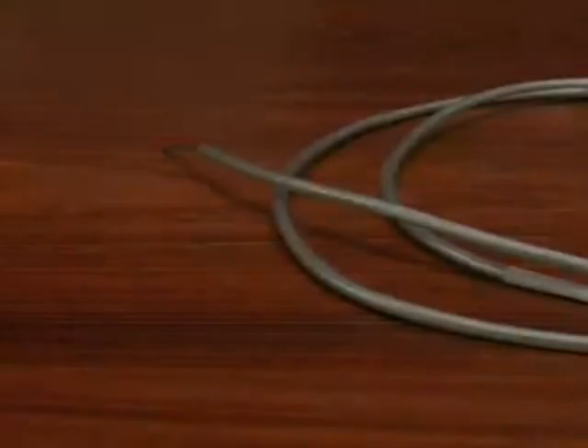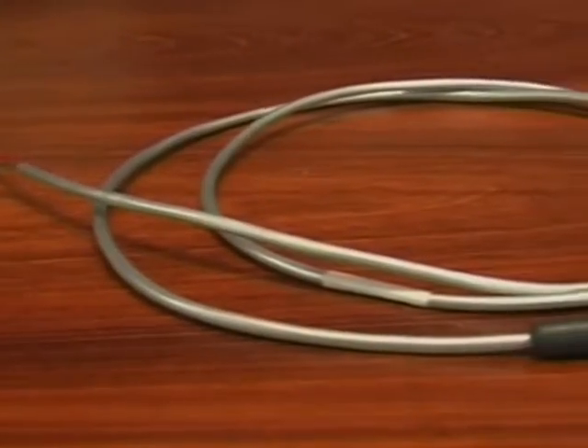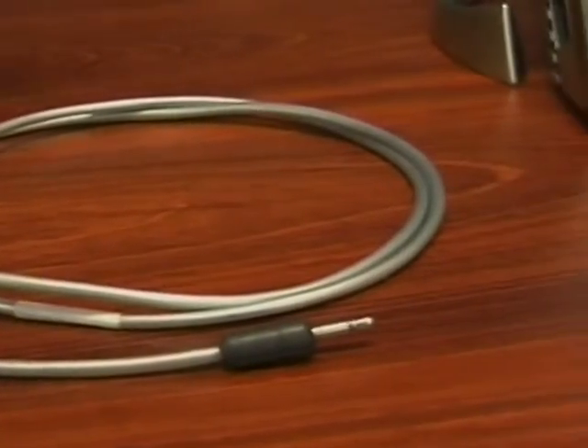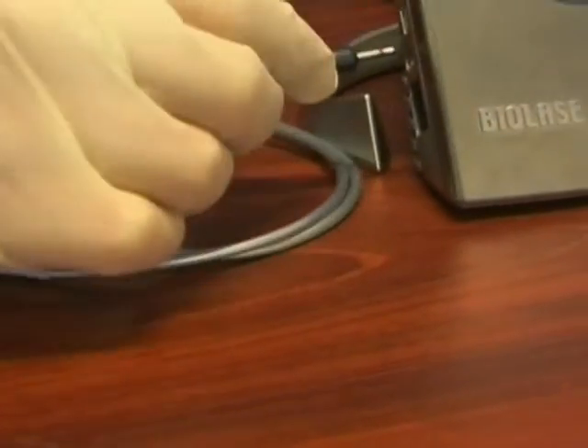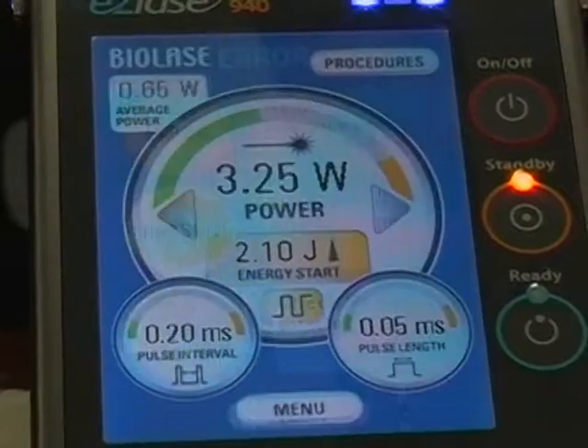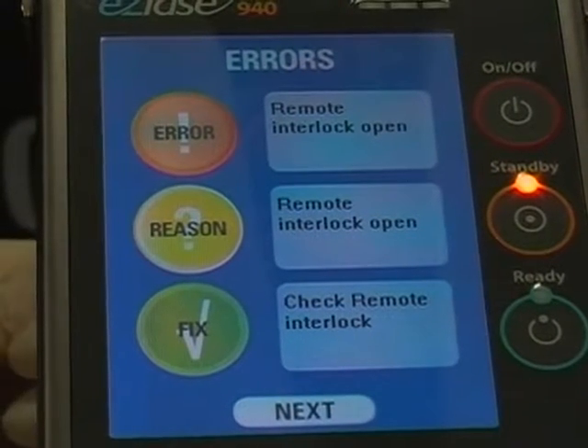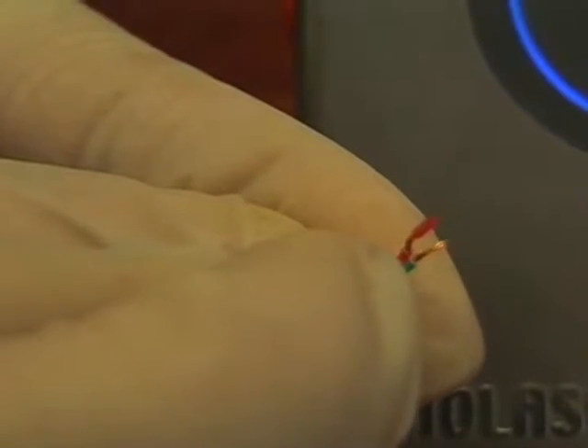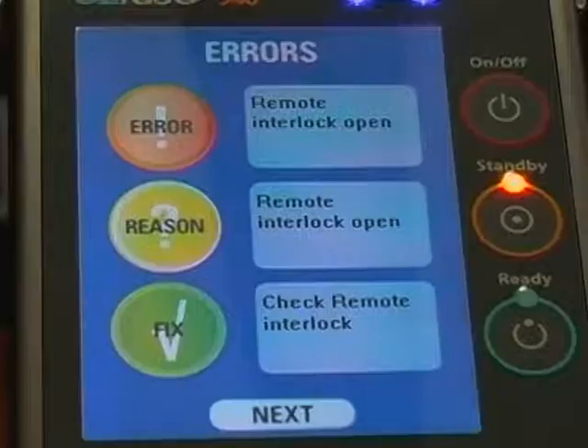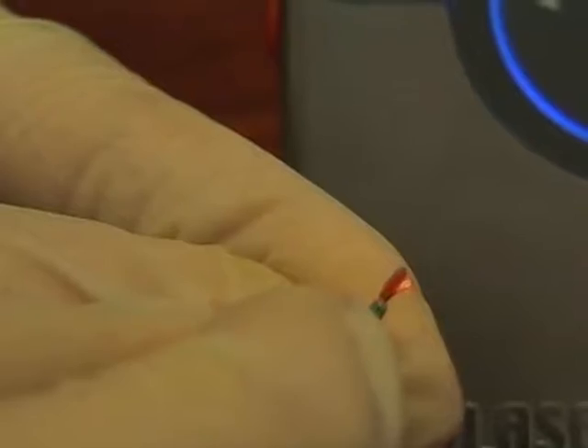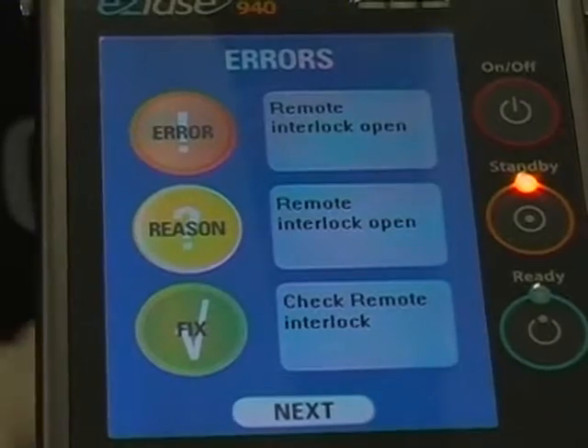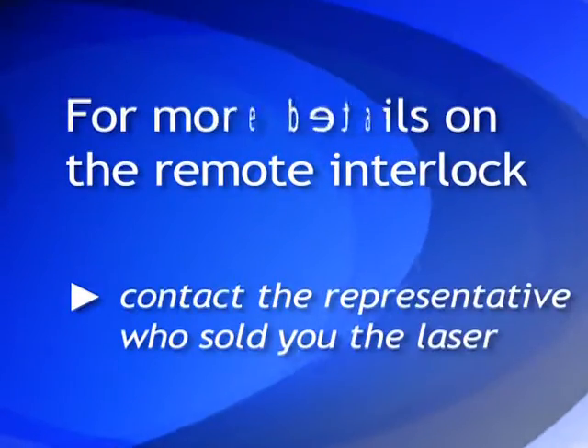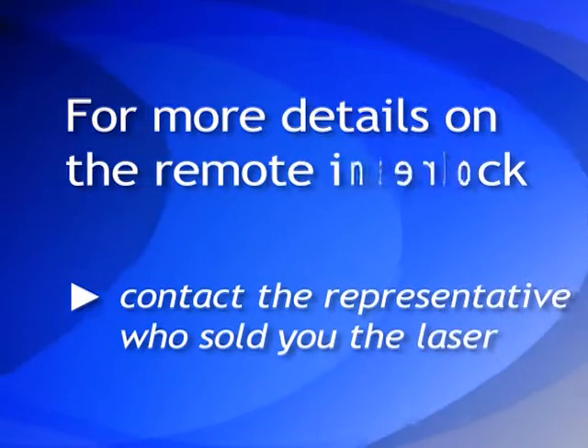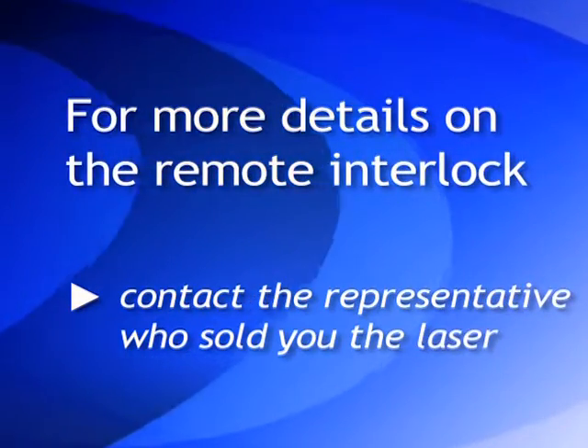The Ezlase is fitted with what is known as a remote interlock. This is a connector on the laser which can be wired to an interrupt switch on the door of your operating room. If someone enters the room, the door interrupt switch will immediately turn your laser off. In some jurisdictions, it is compulsory to fit the remote interlock. To find out if you are legally required to connect it, or for advice for your electrician on how to wire the switch and connect it, please contact the representative that sold you the laser.